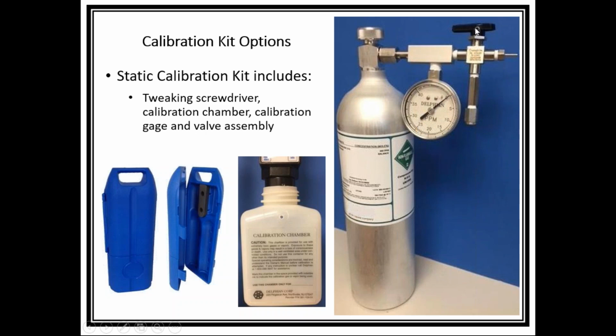And when we turn this three-way valve, we allow this amount of gas that's in this 1.2 cc volume to be expelled through this hole into the chamber. And when it comes to equilibrium, you'll have an exact 25, 30 ppm exposed to your sensor. The beauty of this is that you never really flow a high concentration of dangerous toxic gas over the sensor and expose the technician to those levels of toxic gases. And this is really, really important, especially in confined space entry areas where you don't have that much volume of air to begin with. This type of static kit right now is used for hydrogen sulfide and carbon monoxide. It's also used in mercaptan as well.